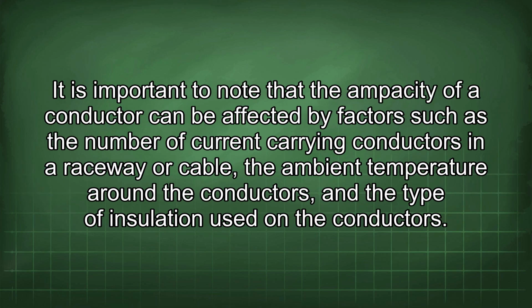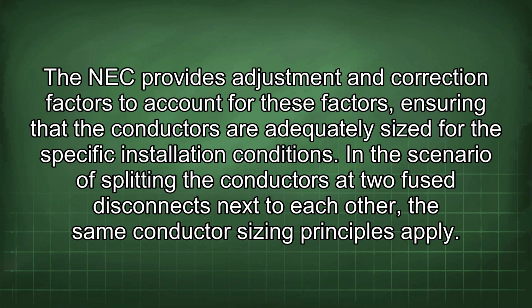It is important to note that the ampacity of a conductor can be affected by factors such as the number of current-carrying conductors in a raceway or cable, the ambient temperature around the conductors, and the type of insulation used on the conductors. The NEC provides adjustment and correction factors to account for these factors, ensuring that the conductors are adequately sized for the specific installation conditions.